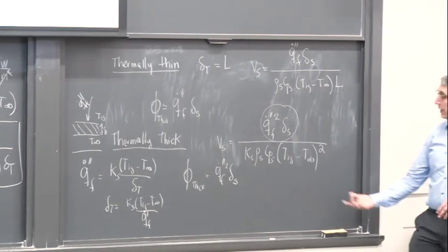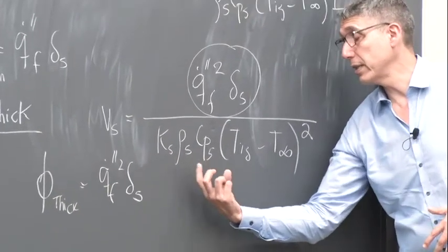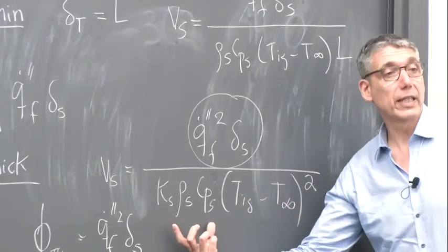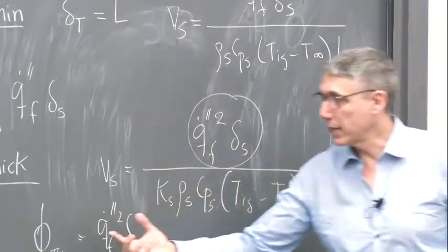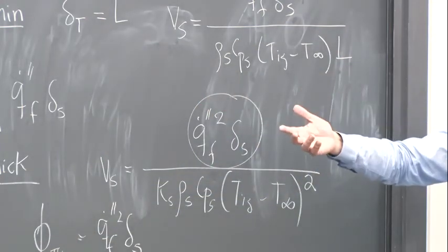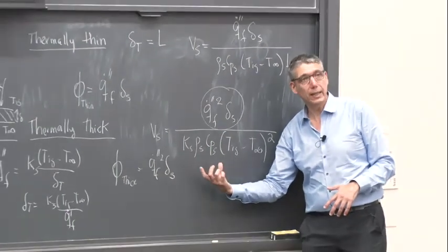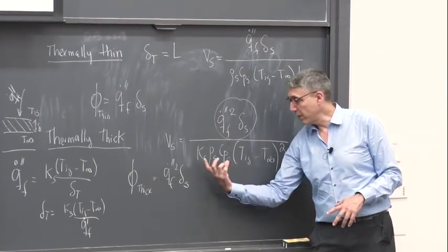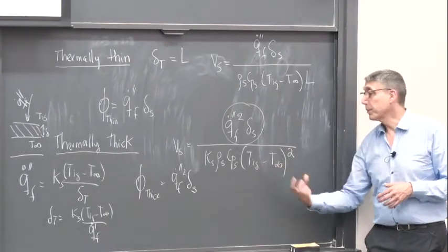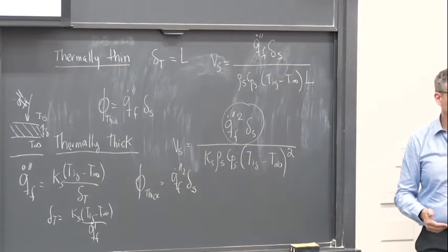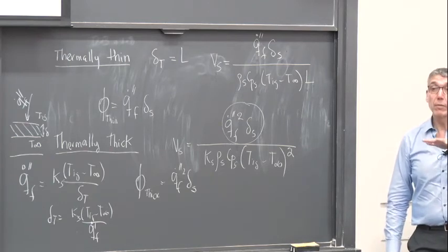Okay? So this is what Quintiere calls the thermal inertia. And it's the product of the thermal conductivity, the density, and the specific heat. Now, in this particular case, he's assuming global or average properties. So he's not discriminating the fact that as you go deeper, you're going to be colder, and therefore the properties are going to change. So these are effective properties, okay, which ends up being a little bit of a problem that needs to be addressed. This is the ignition condition, the fast chemistry, okay? And we have an expression for the flame spread velocity for both types of materials, okay? So everybody's comfortable with that?